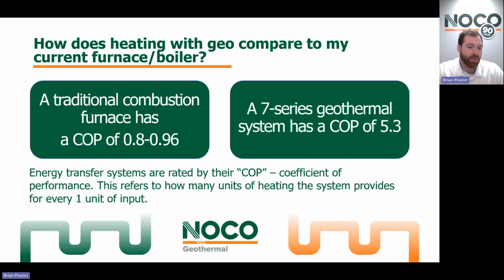So for combustion furnaces or boilers, we usually see that 80 to 96% efficiency rating. That means a coefficient of performance between 0.8 for 80% to 0.96 for 96% efficient. What that means is of all the natural gas, propane, heating oil that's being combusted, you're only getting 80 to 96% of that heat. So where's the rest going? You're usually losing a little bit during the combustion process to byproducts. The byproducts you create gunk up the combustion portion of your furnace or boiler, the combustion chamber. You might have a cracked heat exchanger.